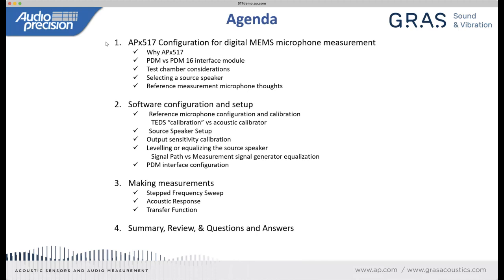But in general, most of what I'll demonstrate today will apply to any situation in which you want to find the basic parameters, the frequency response, phase response, and sensitivity of a microphone. I'll talk about the prerequisites for that task, physical prerequisites, peripheral devices. And in this case specifically, we've announced the APx517 acoustic audio analyzer, which is particularly optimized for this task.